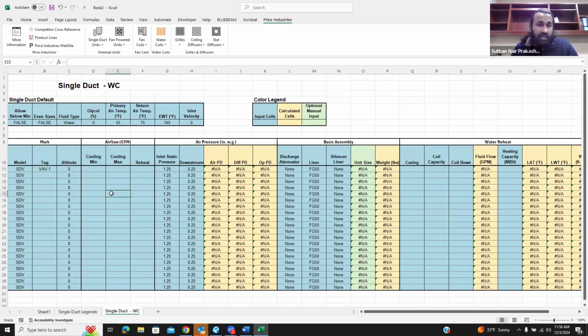So VAV1, and here I can have the cooling minimum as 500, cooling max is 1000, reheat at 500. And these are your industrial traditional standards as well, the static pressure and the downstream pressure. And you guys have the options to pick all this discharge attenuator, liner, and silencers. But when you see here, there's multiple different FF1, FF50. It might be hard for you guys to figure out what these liners are.